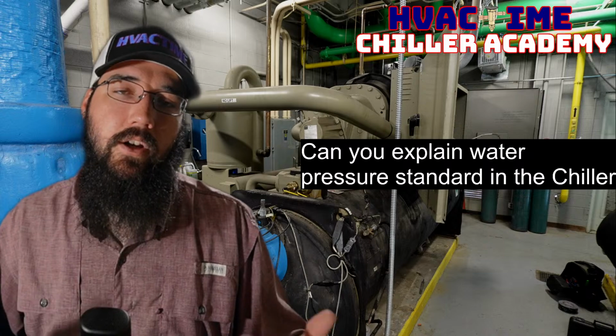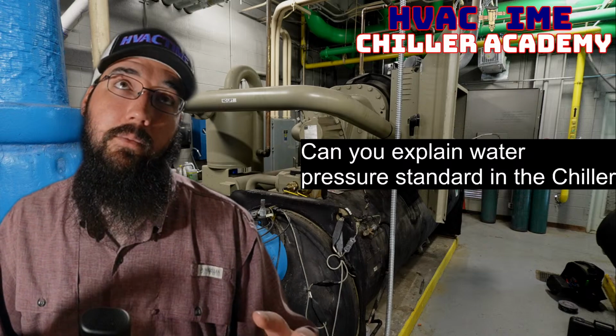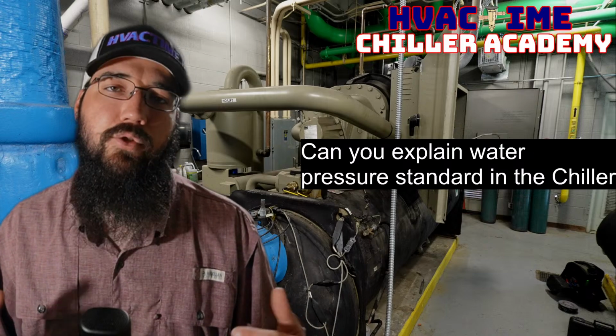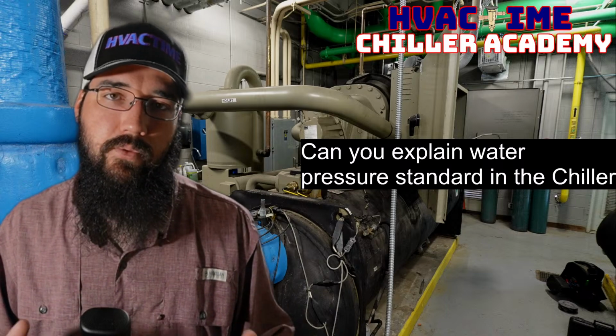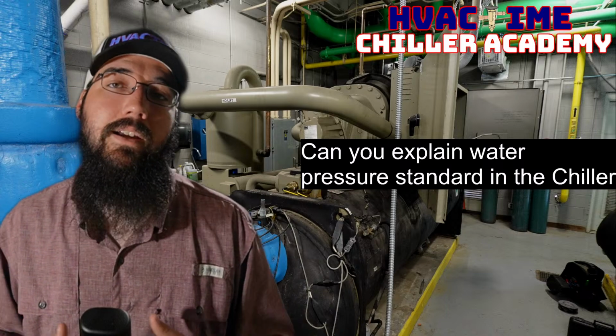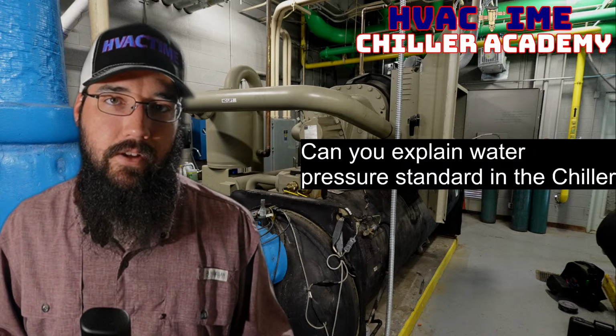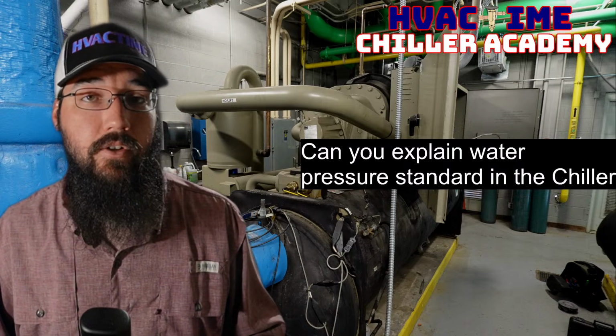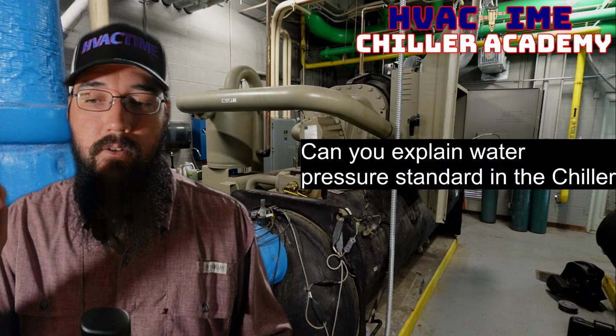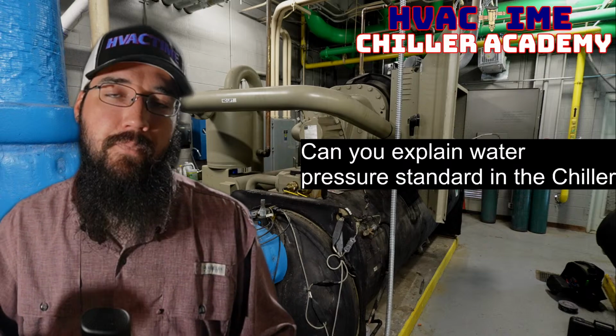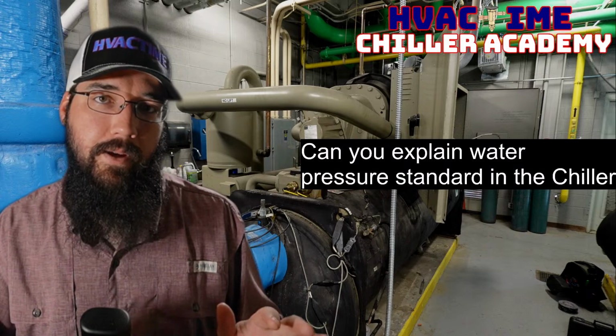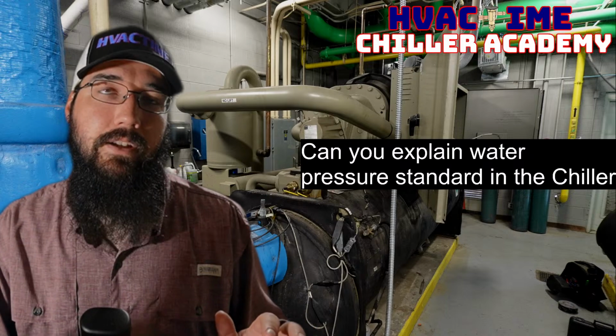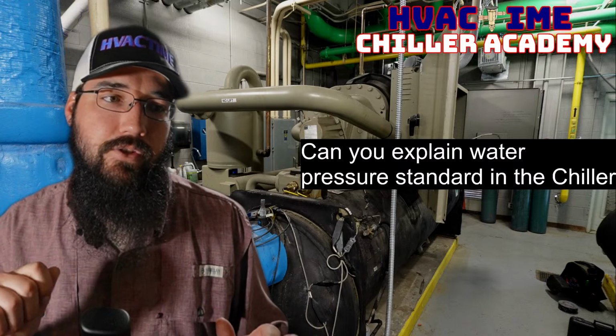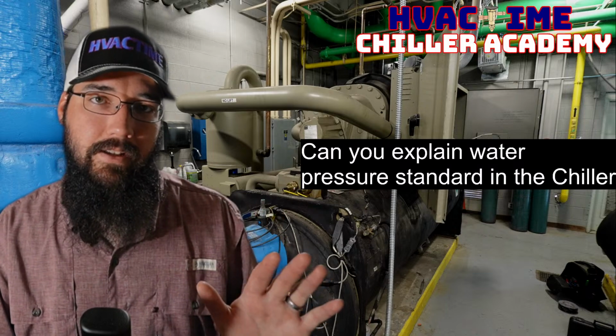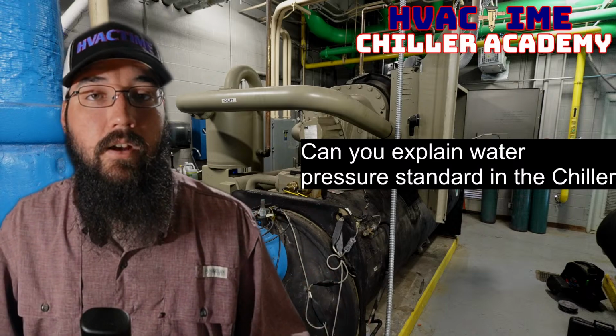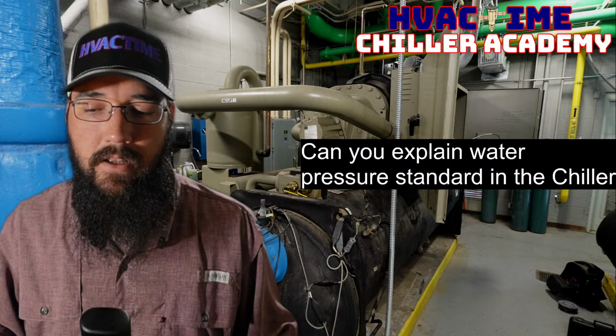So the only other alternative, or let me rephrase, another alternative is you can get the actual sales information for that machine and what it was spec'd for. Technically, the customer should have that on file somewhere. Sometimes the startup technician will write that in the panel. So inside of the control panel, he may write what the design DP is and GPM and what all that data is. He may actually do that, and that would be really helpful if everybody did that.